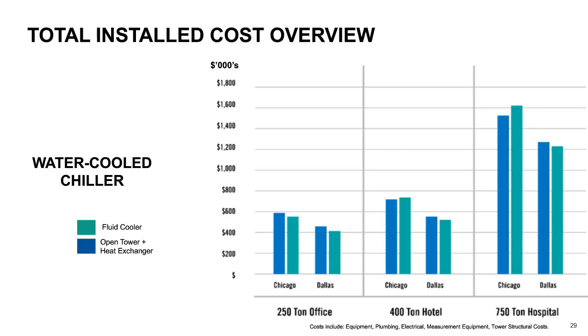Okay, thank you, Andrew. Now we're going to look at the total installed cost overview for the two types of systems that were studied. The first being the water-cooled chiller option. And what we have here are graphs of total installed cost, and this is just total installed cost for the heat rejection portion of the system. And the y-axis is the cost in thousands of dollars. The fluid cooler is shown in green, and the blue bar is the cost for the open tower heat exchanger. So, for the 250-ton case, the fluid cooler was less costly on an installed basis in both Chicago and Dallas.